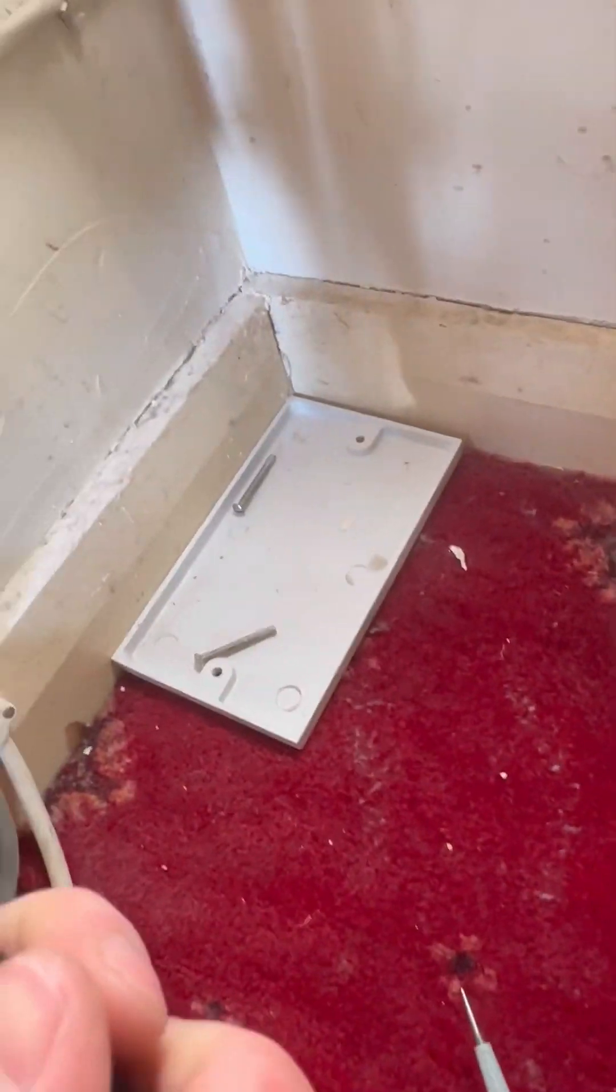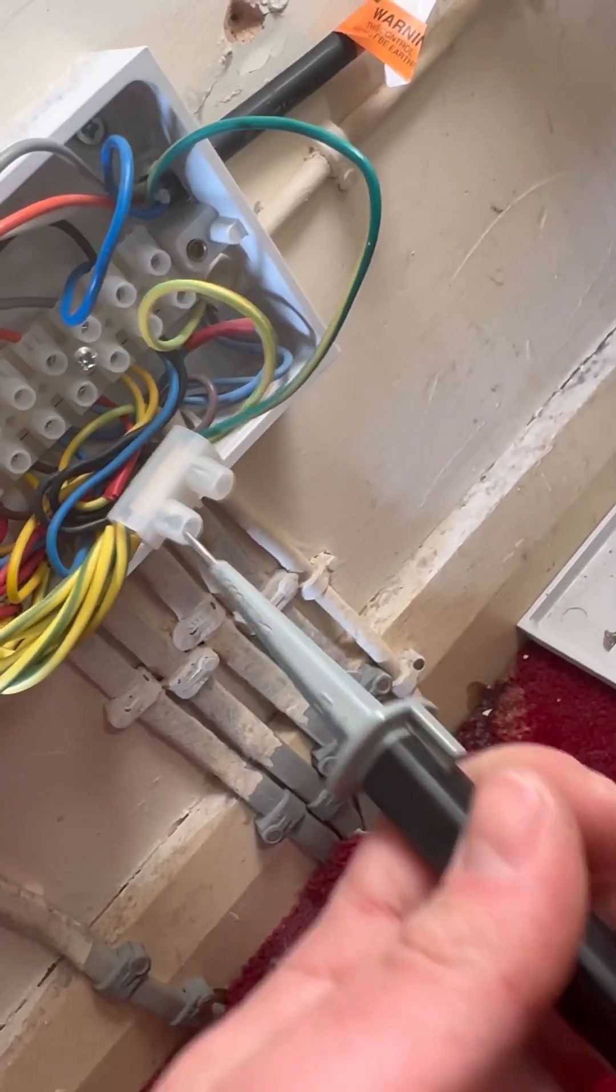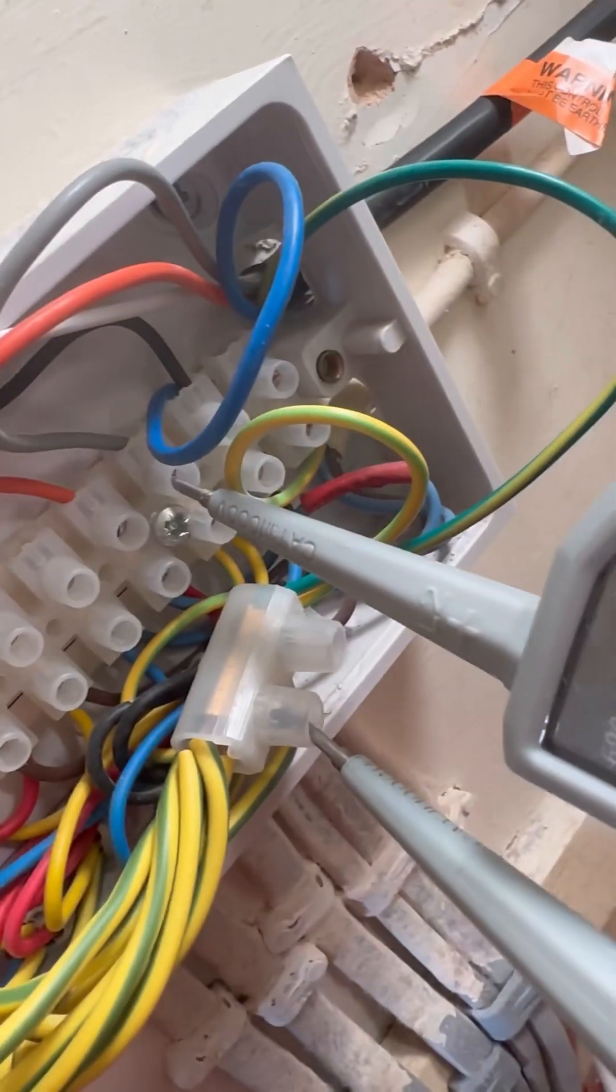So we'll turn the cylinder stat down and then that just proves cylinder stat and programmer are doing their job. So we'll do earth to gray. We're looking for 240 at this point. Yeah, so that's good.